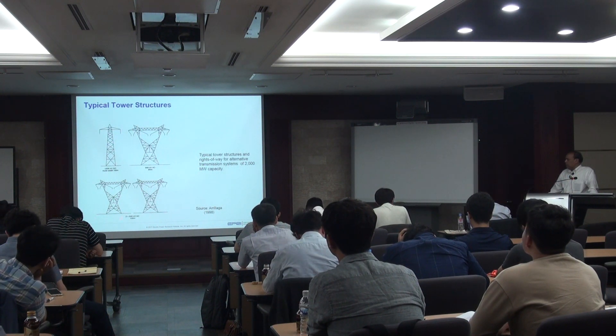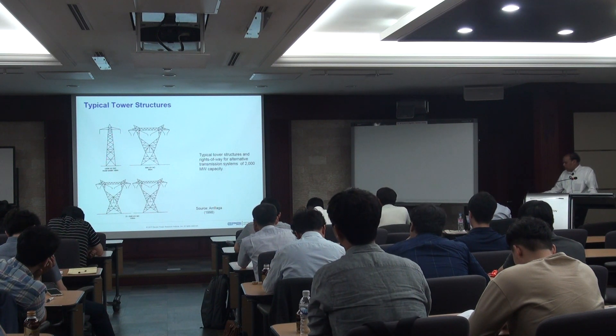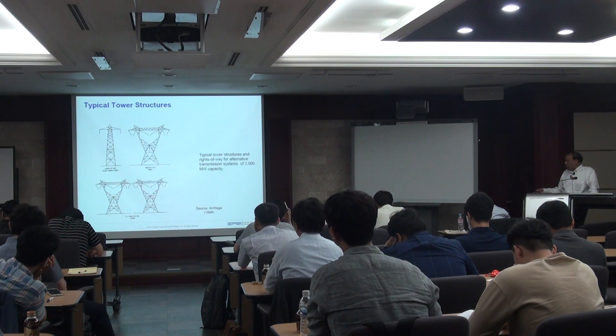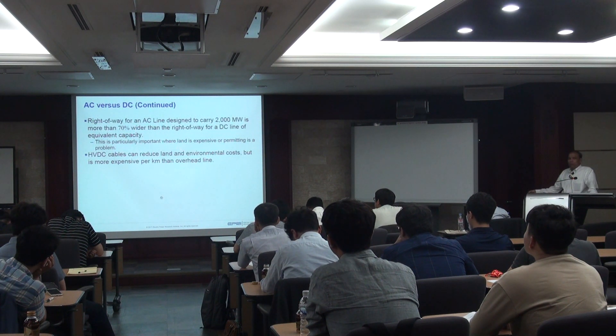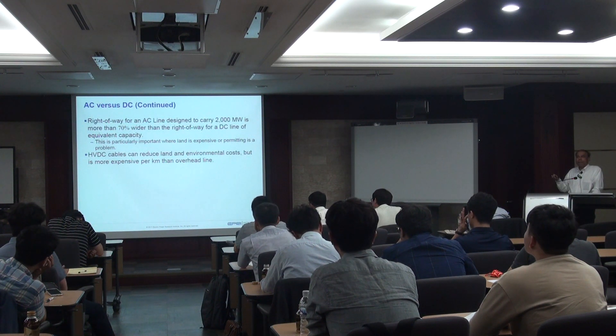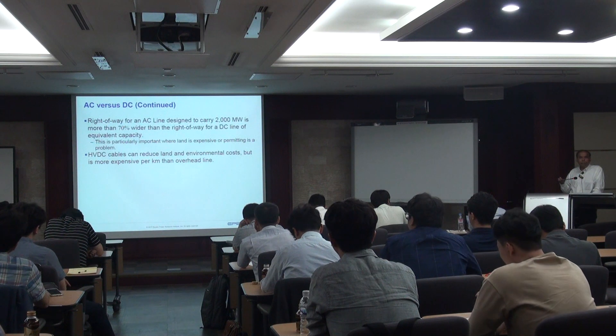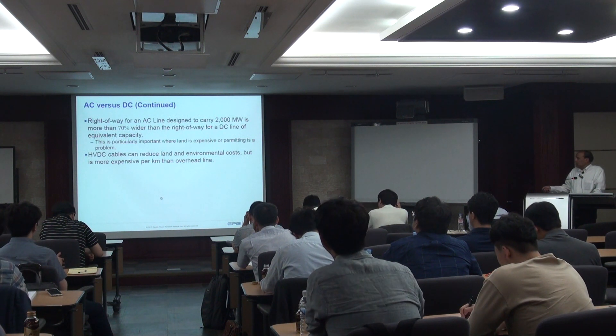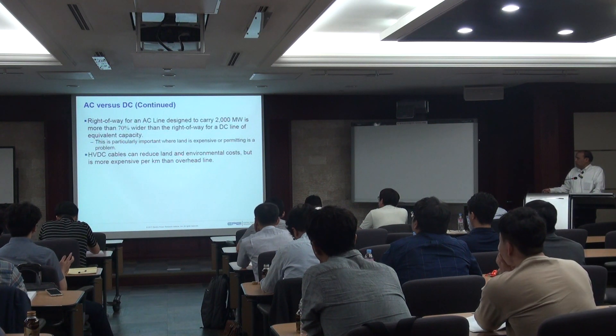For typical power structures carrying 2000 megawatts — comparing 500 kV HVDC against two 500 kV AC circuits — the DC tower structure is simpler and occupies less space. In general, the right-of-way for AC is more than 70% wider than for a DC line of equivalent capacity. Getting new right-of-way is very difficult today due to environmental issues and public opposition, which also contributes to the decision of building AC versus DC.